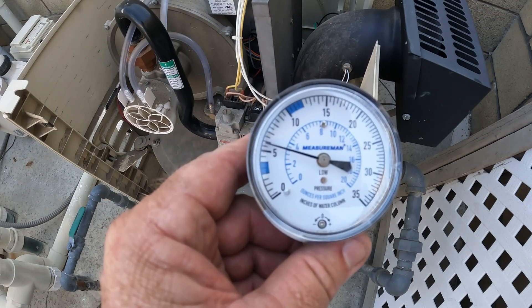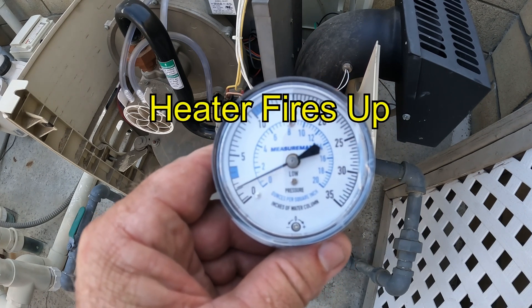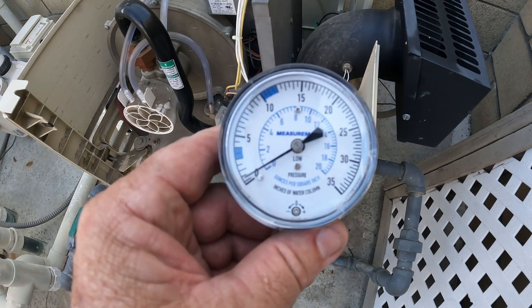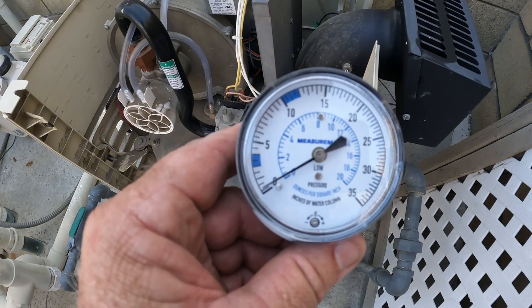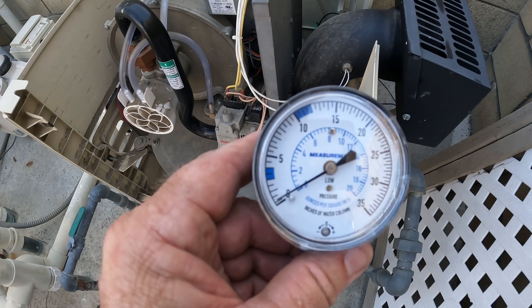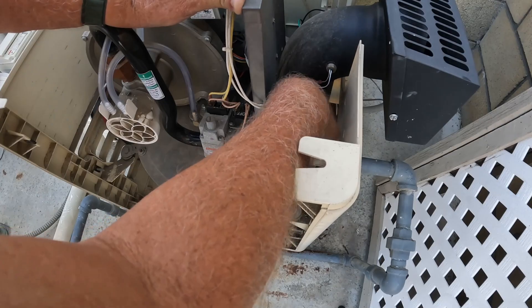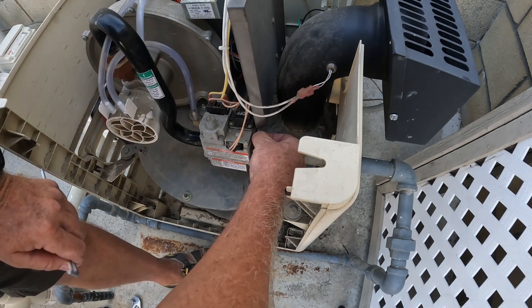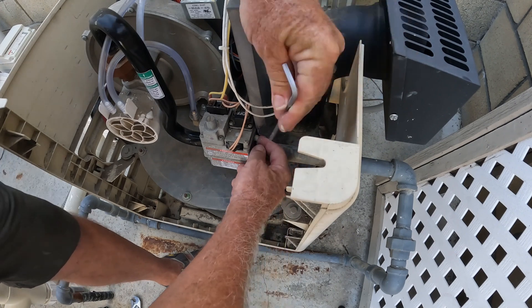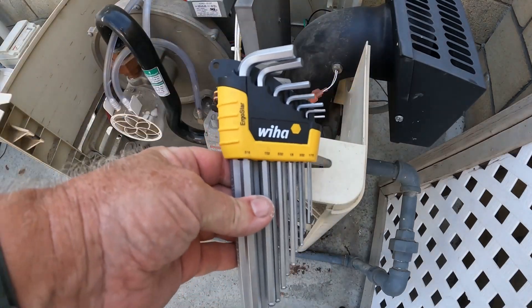Now let's run the analog meter on this. We've got a point six inch water column there, and that's already too low for a static water column reading. We're coming down to again less than one inch water column. We need a four to fourteen inch water column for this heater to run right. This heater being that low will run hot — it's no different than a car where you don't have enough gas going in; you're going to be running lean. So this heater is going to have problems.